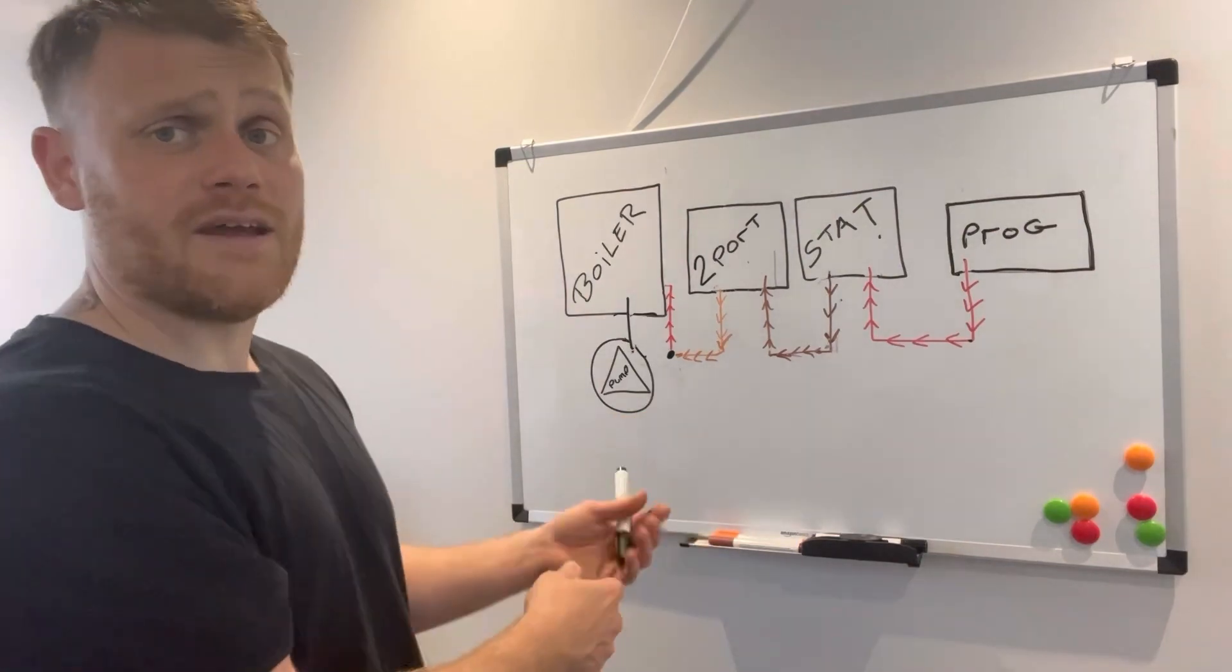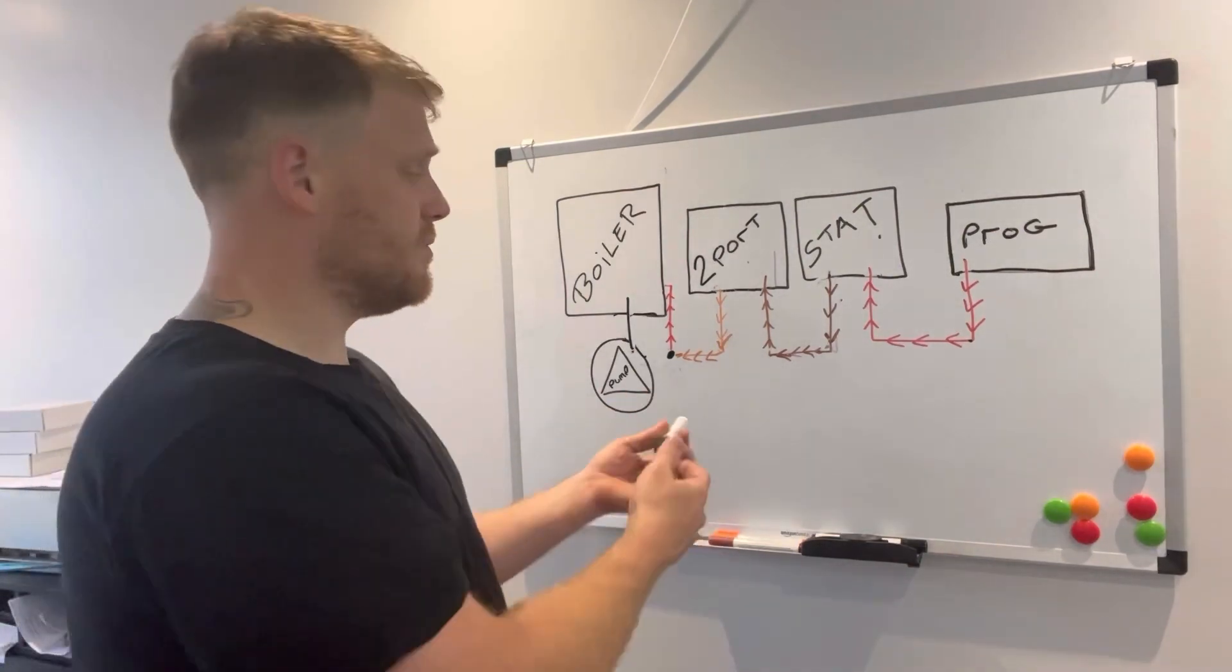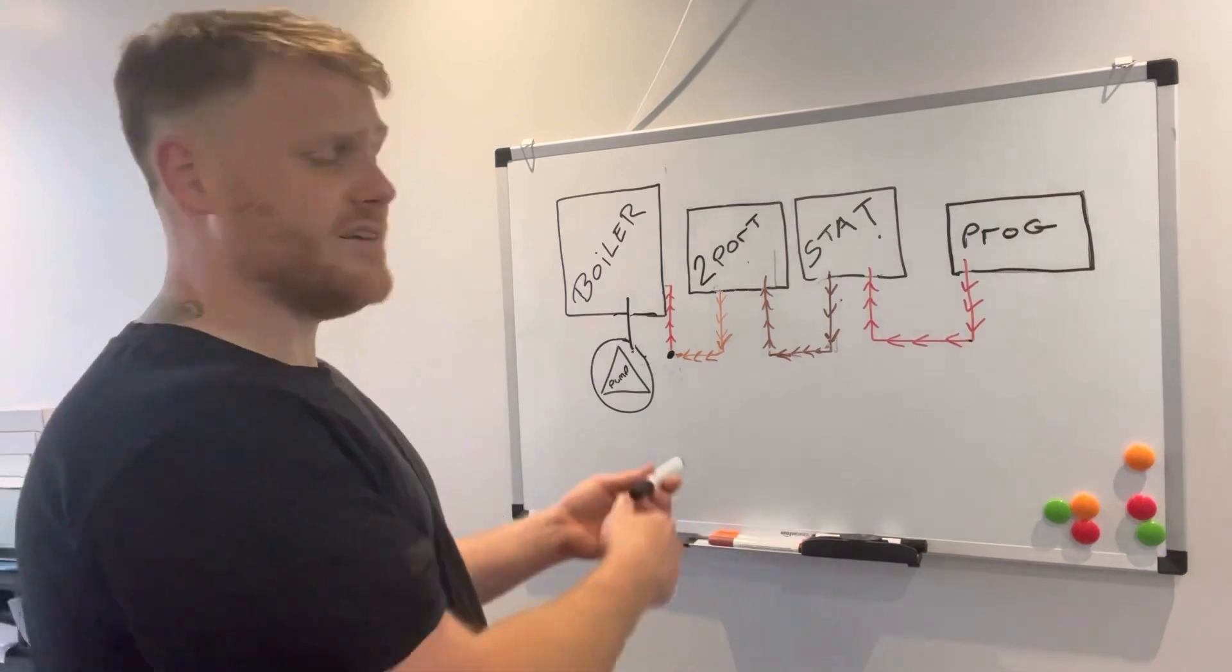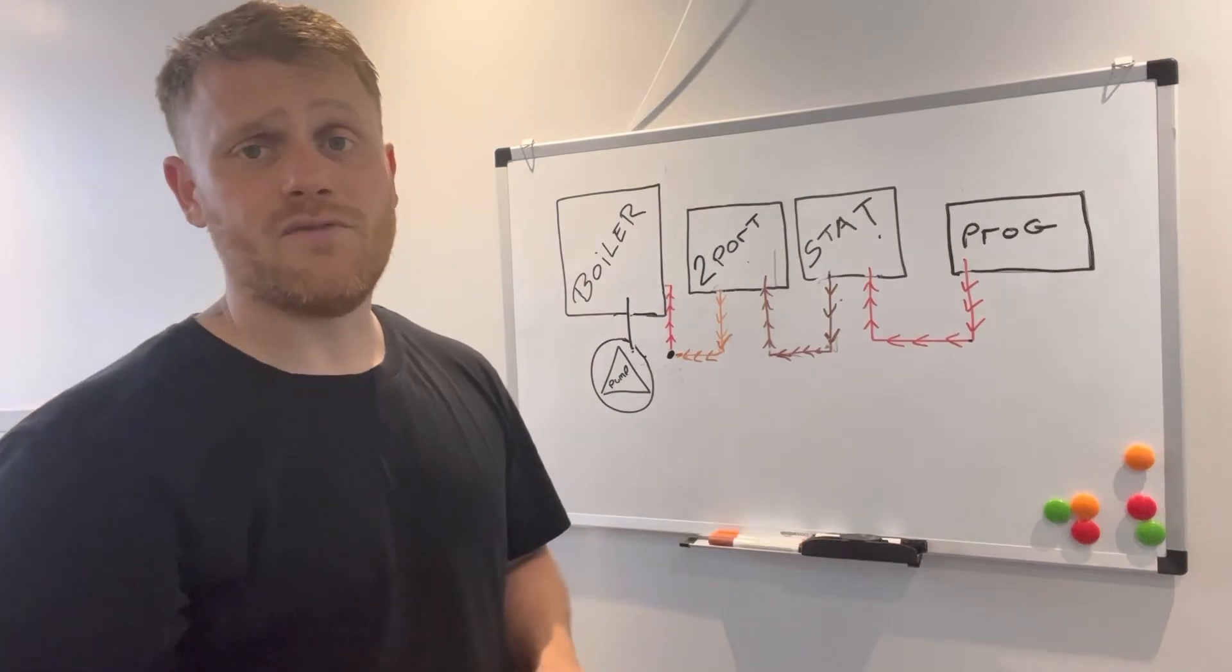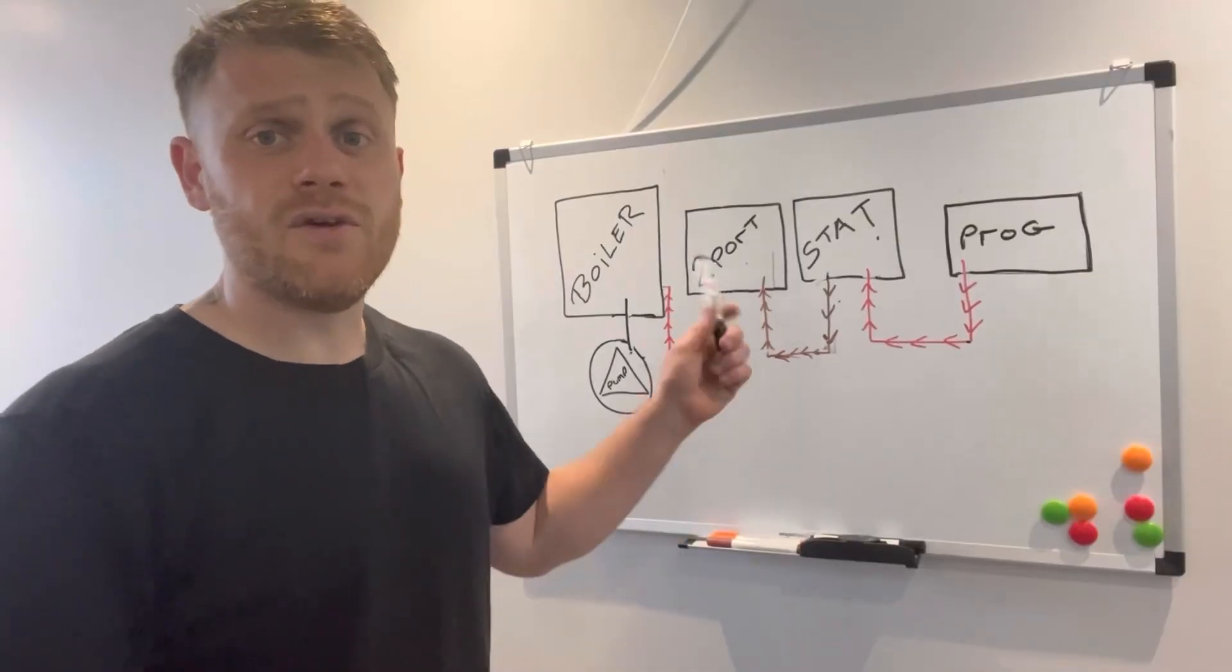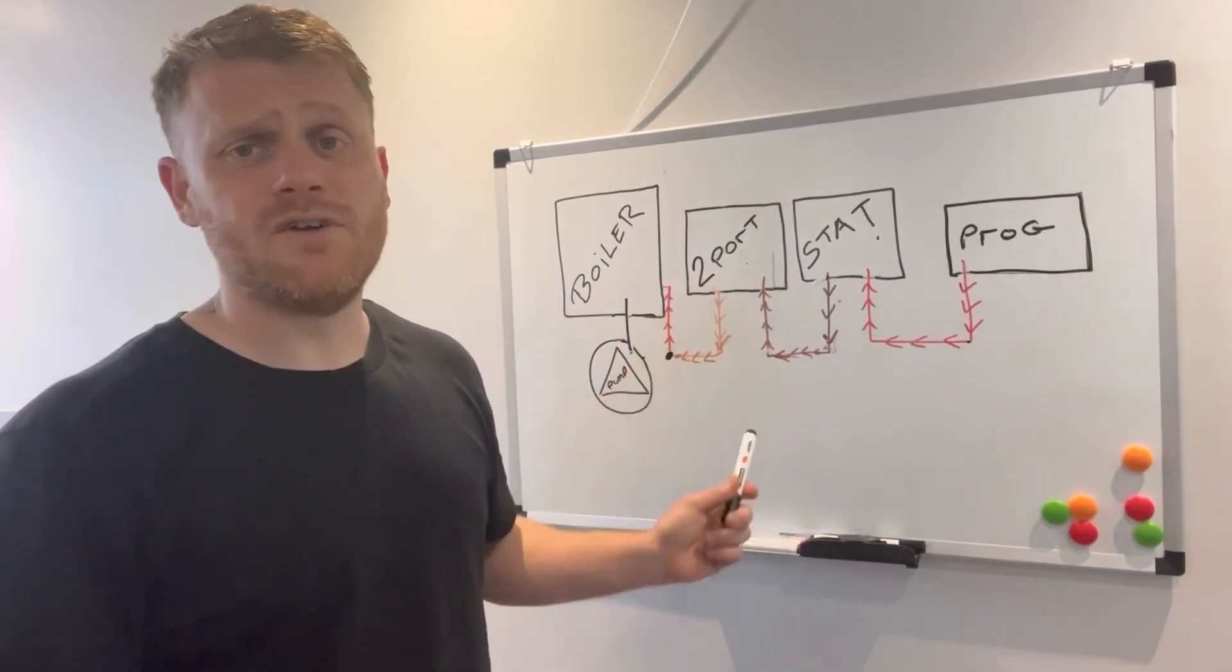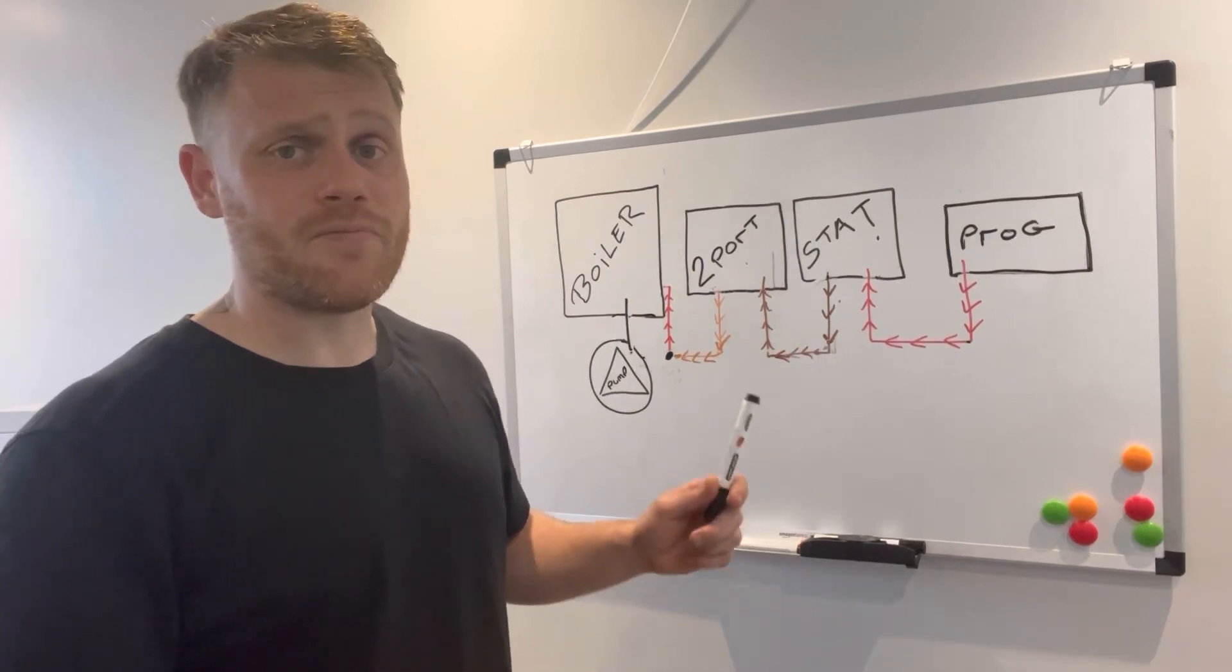Obviously if it's 240 here, the boiler should be coming on. Fault finding becomes a lot easier once you understand electrics. When you turn up to a fault on these and say the hot water's working but the heating isn't, you can just get your probes out, start testing, and you can find where the fault is really easy.